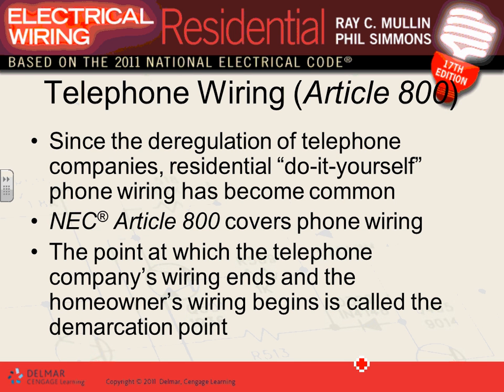Okay, any comments about the cable TV? To summarize: cable TV coaxial cable must be completely separated from the power and light - we talked about this. It must not be terminated in any box with power and light unless you separate them. It must be grounded as it enters the building, supported to the dish as well as supported as it enters the building, and grounded at the demarcation point. Any comments before I move into telephone wiring?